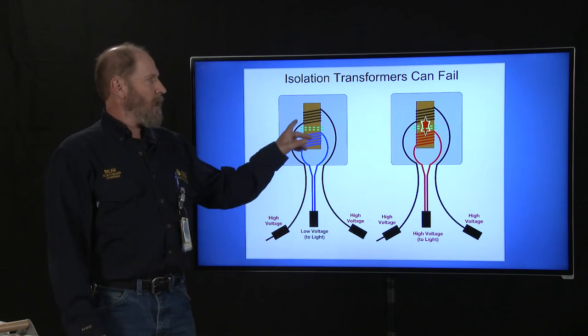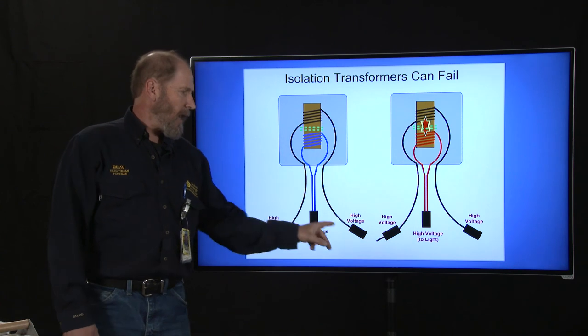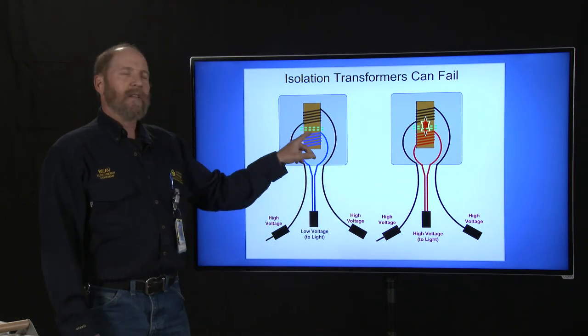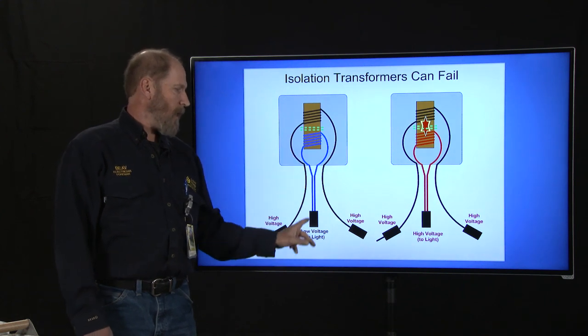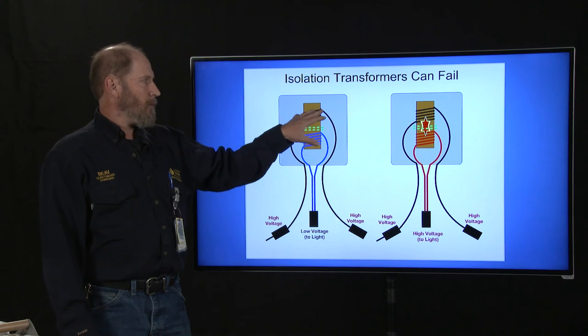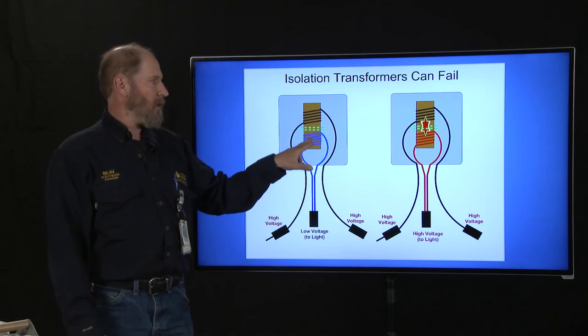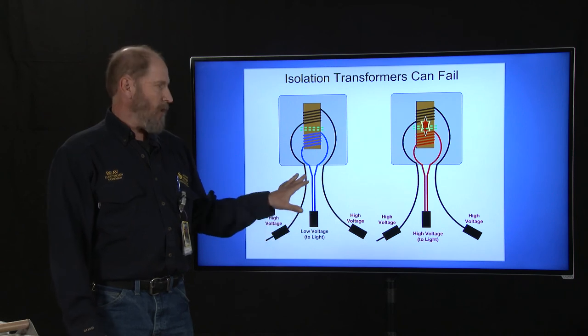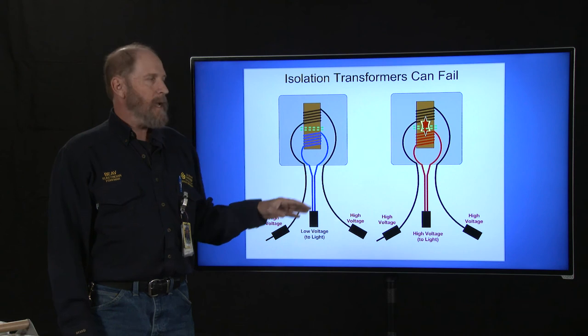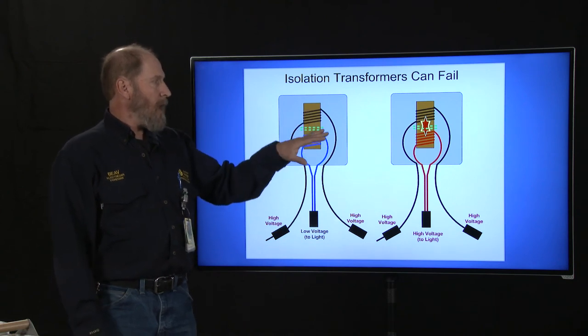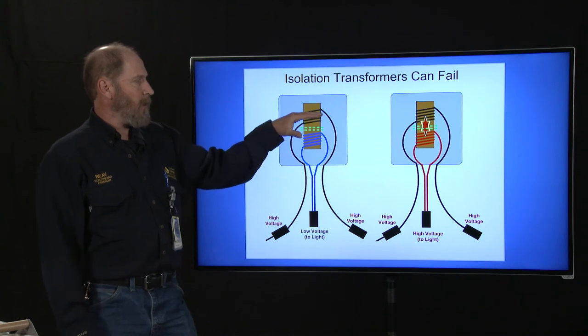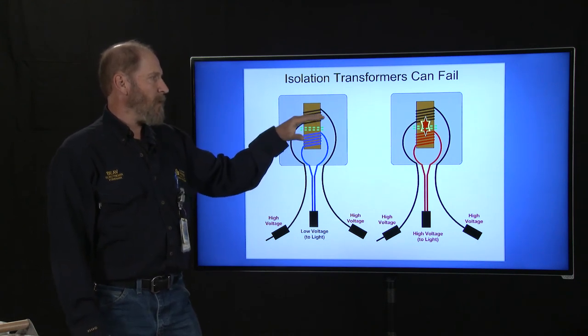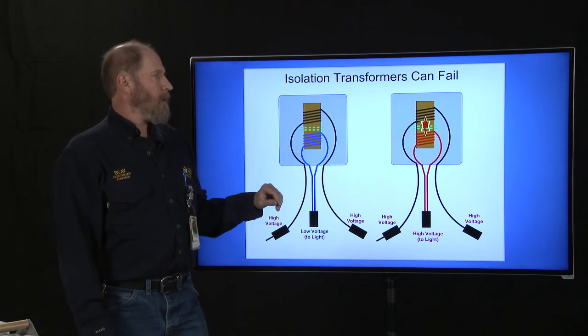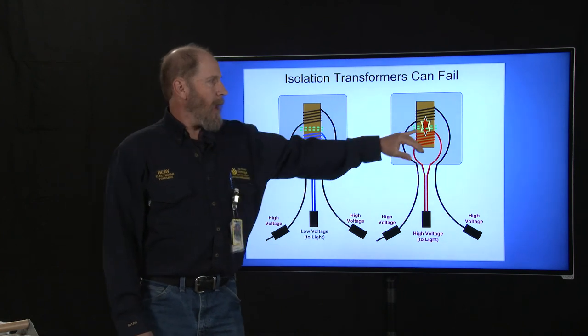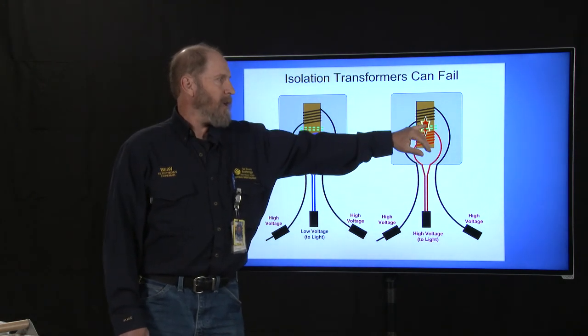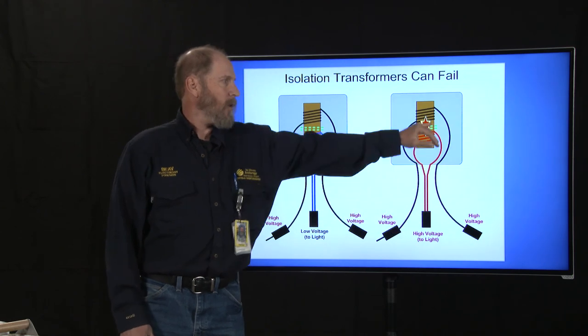The high voltage comes in and it wraps around an iron core and then it goes back out and it goes on to the next fixture. On that same iron core, you have a wrap of wire that comes out and goes to your light and back. And that high voltage is reduced and induced into the low voltage side. It all works fine until something goes wrong. Now these wires are in very close proximity to each other. But I should also say that there is no transfer of energy directly between the primary side and the secondary side. It's insulated. But something can go wrong, and if we have a breach there or a fault, it's very easy to put high voltage into our secondary side.